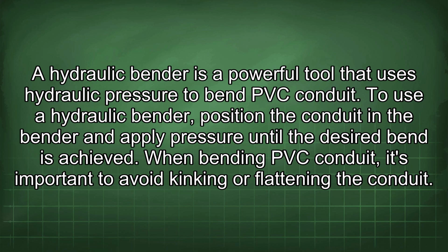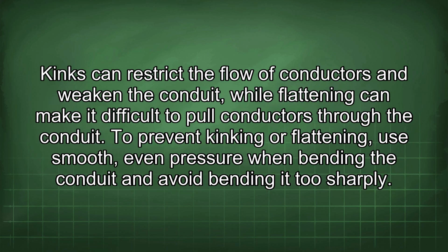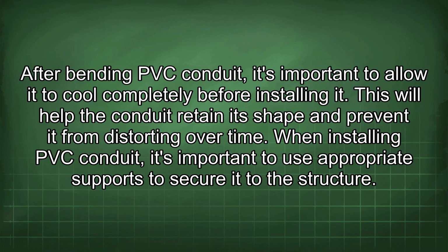When bending PVC conduit, it's important to avoid kinking or flattening the conduit. Kinks can restrict the flow of conductors and weaken the conduit, while flattening can make it difficult to pull conductors through the conduit. To prevent kinking or flattening, use smooth, even pressure when bending the conduit and avoid bending it too sharply. After bending PVC conduit, it's important to allow it to cool completely before installing it. This will help the conduit retain its shape and prevent it from distorting over time.